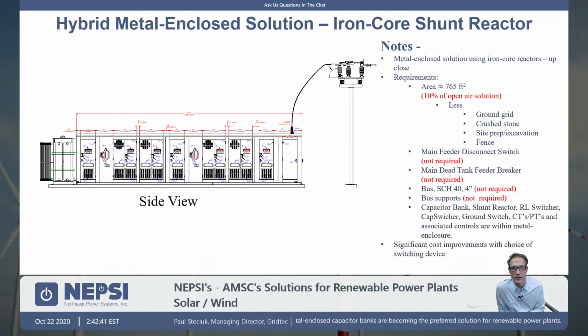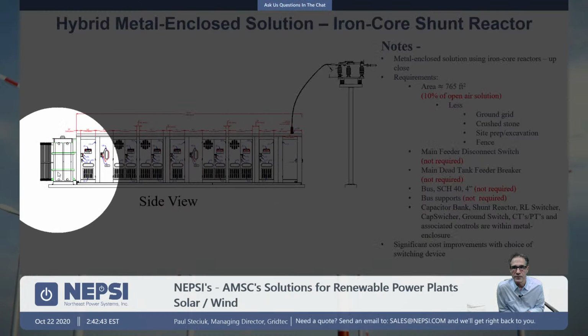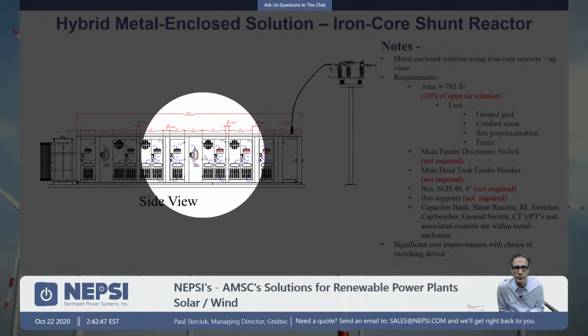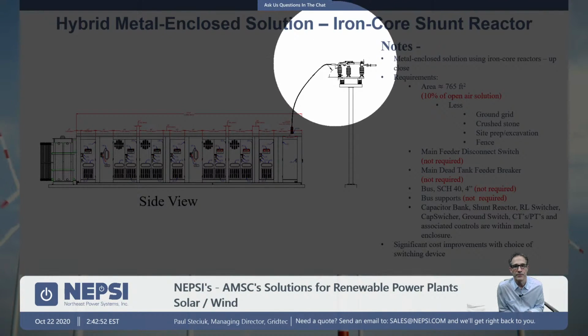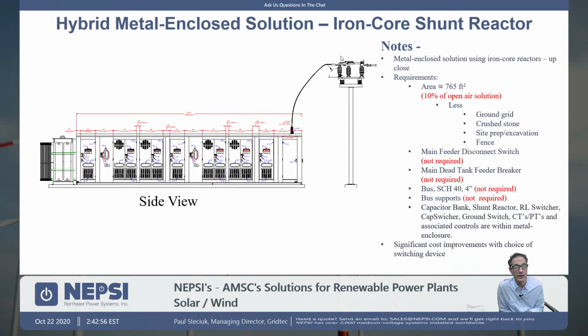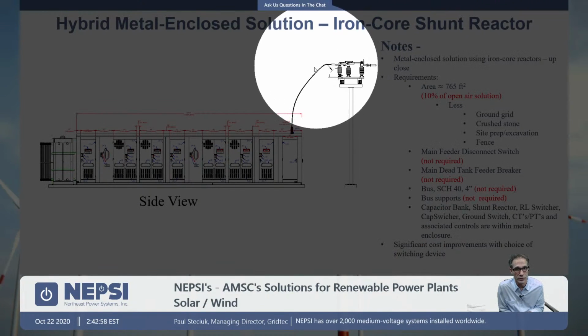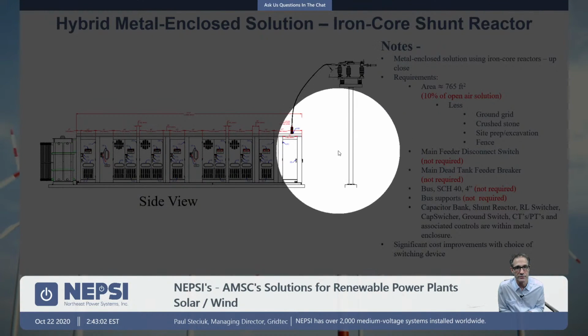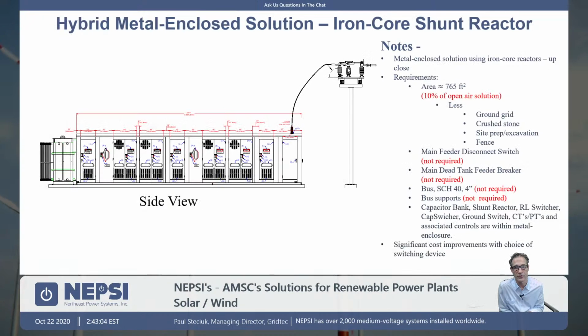So just a side view here, shunt reactor on the end. The 2 capacitor stages here, you can kind of see the ground switches with windows, and we have roof bushings coming in, going to the overhead gang operated switch. And again, we show this gang operated switch. We could push that gang operated switch down into the enclosure here and eliminate that also. So another savings and cost savings opportunity.